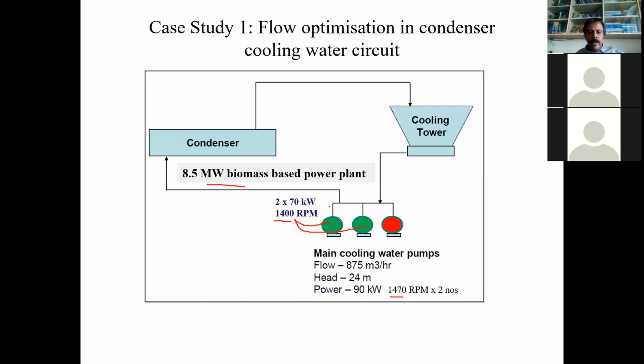If one is operating at a higher speed and the other at a lower speed, then this pump will not be able to pump water into the header, because your head is proportional to the square of the speed. When you reduce the speed, the head also comes down. So in order to effectively utilize the VFD in parallel pump operation, it is ideal to have a common VFD for both the pumps. In case that is not possible, you can have a separate VFD, but ensure that both the VFDs are operating at the same hertz or the same speed, so they synchronize with each other and pump an adequate quantity of water. Now it is at 1400 RPM, drawing 70 kilowatts.